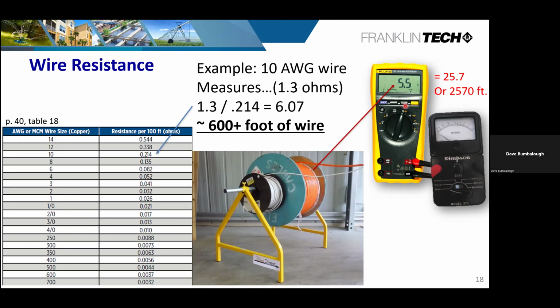And the example that I've popped up here, let's say we're looking at a 10 gauge wire. I pull up my chart, and it says for every 100 foot, I'm going to get a resistance value of roughly 0.214. So on a spool of wire, I go out on the end where there's typically the first part of the wire sticking out. I'm going to strip it back and put a wire nut on it, and at the other end, I'm going to put my meter onto it. In this exercise, I got 1.3 ohms. So I know it's a 10 gauge wire. 1.3 divided by the 0.214 says I roughly got 6. So 6 times 100 says I've got about 600 foot of wire on that spool. And that's how you would determine how much is left on there.